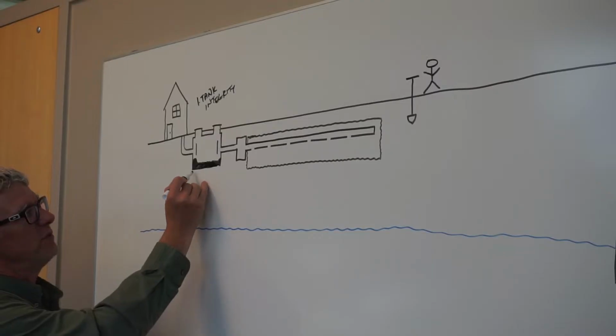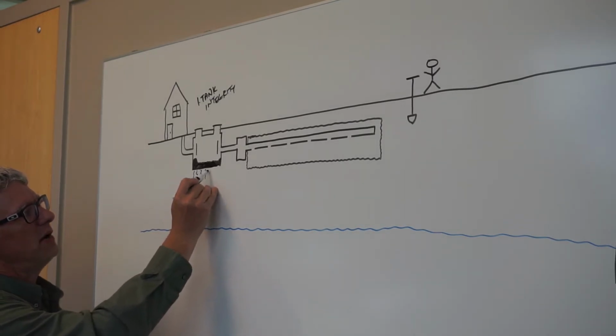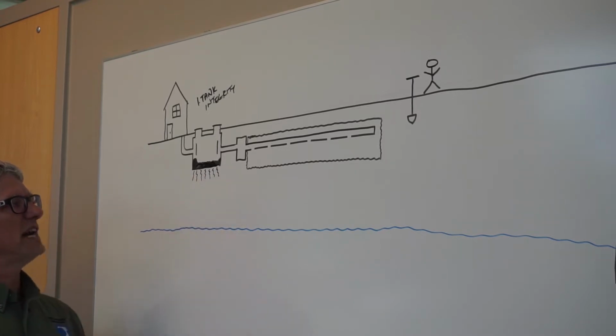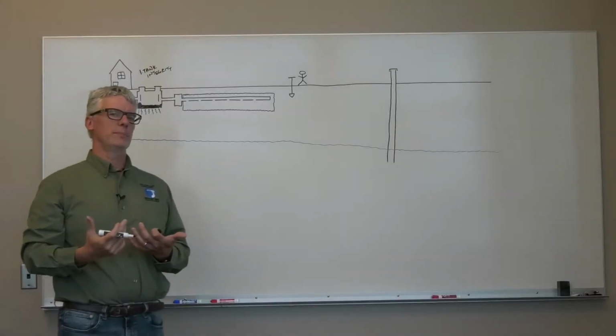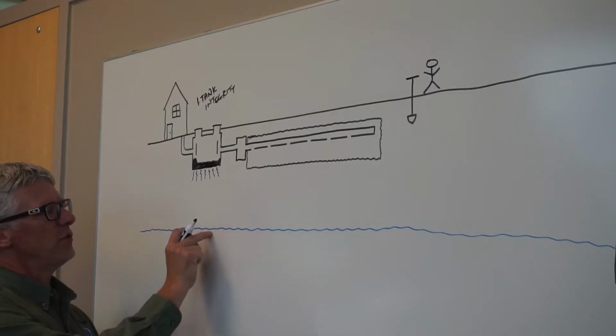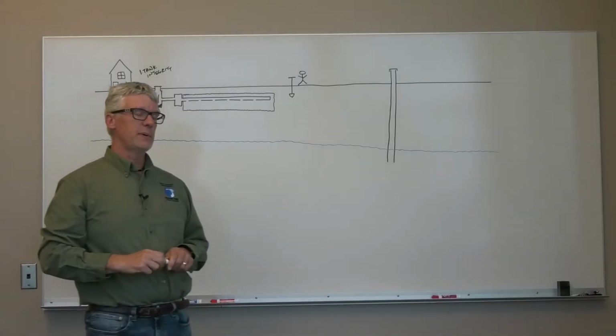Because the septic tank effluent is going to leave the tank and again create this area underneath the tank that is heavily saturated, and when you have saturated soil, you're not getting any treatment. Therefore, the effluent that's leaving the tank isn't treated before it hits the groundwater. So that's item number one on a compliance inspection.